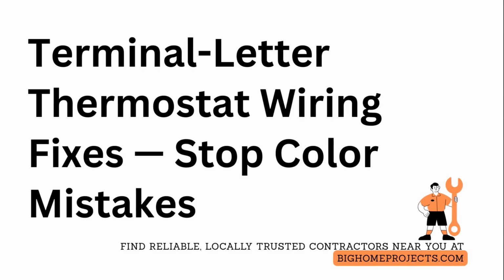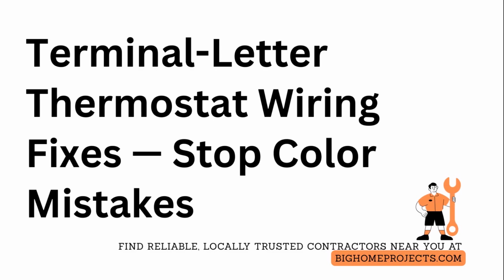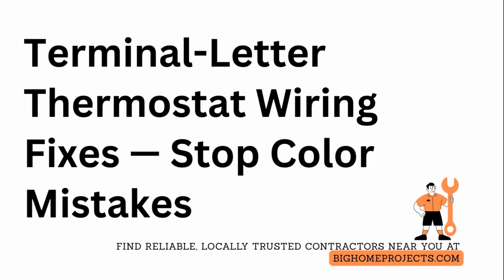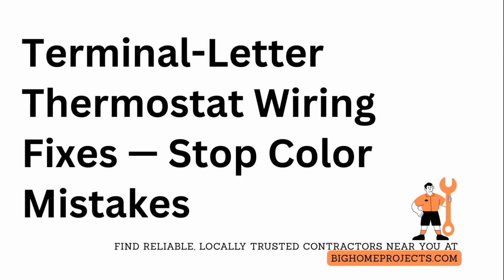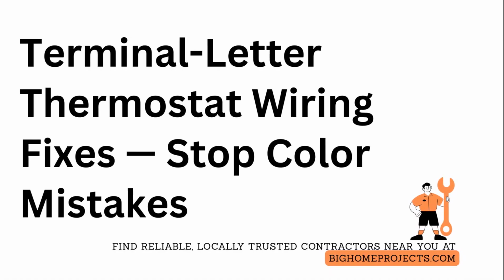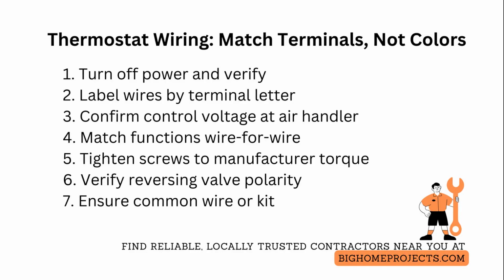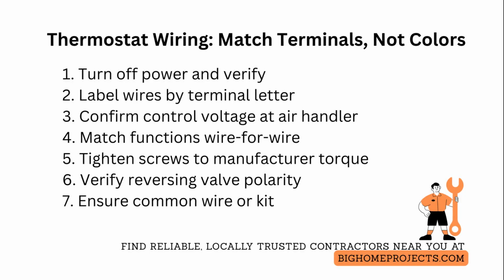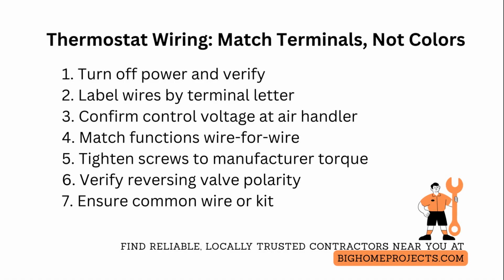Upgrade your thermostat without guesswork. Match terminal letters and voltages, not wire colors, to avoid system damage and unreliable heating or cooling. When replacing a thermostat, start by turning off power at the furnace or air handler and the circuit breaker, then confirm power is truly off with a non-contact tester at the control board. Do not rely on the old thermostat being dead.